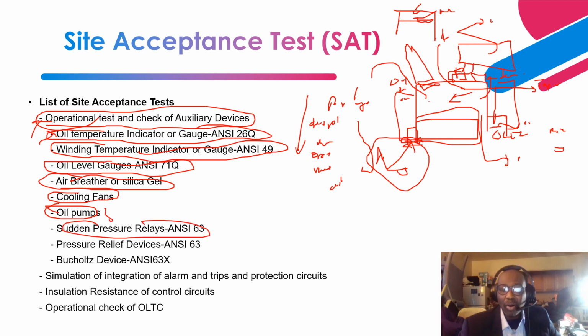Those are located on the sides of the transformer, right? That is able to detect incipient, gradually evolving faults, right? Okay, because some of the faults might not develop enough current. The driving voltage is so small that it basically will not be able to generate enough current, so the differential might not see it. That is when the sudden pressure relay is able to detect this fault.